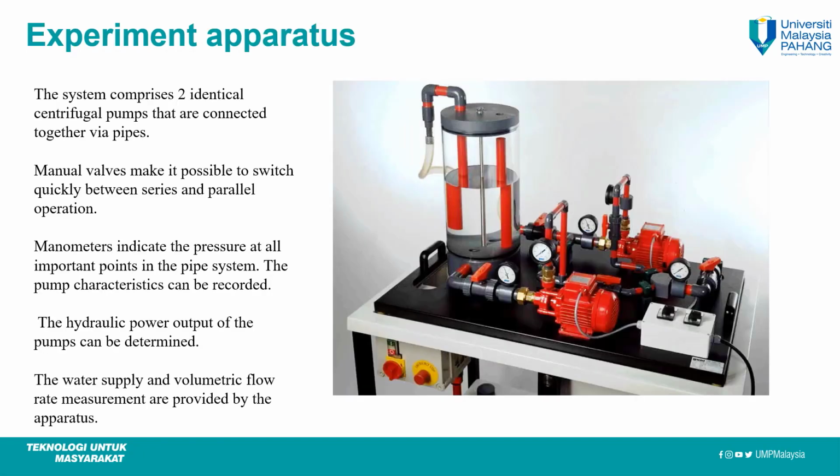For the experimental setup, we have a centrifugal type of pump. The mode of operation of this pump is based on the flow principle. Here we have water as the fluid, so the delivery medium, water, is set in motion by a driven blade wheel with an angled blade which rotates in a helical housing. So we have an impeller within a housing. The water is accelerated by centrifugal force and is fed into the delivery pipe.